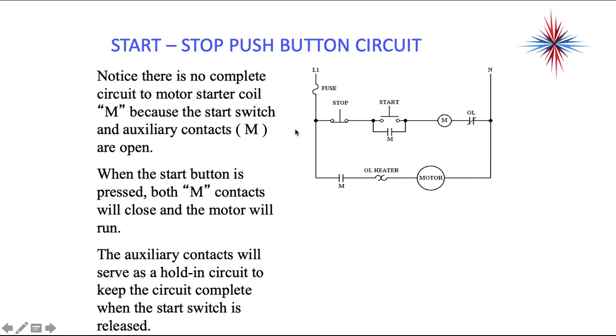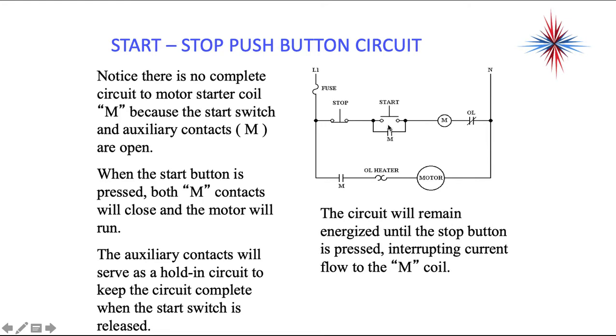When the start button is pressed, in other words, someone presses down here on the start button, the contacts will close and the motor will run. What we do here is we complete a path of electricity to my motor relay coil. That, in turn, closes M. Notice they're all labeled M. So when this coil is energized, we're going to close M and M, and we're going to run the motor.